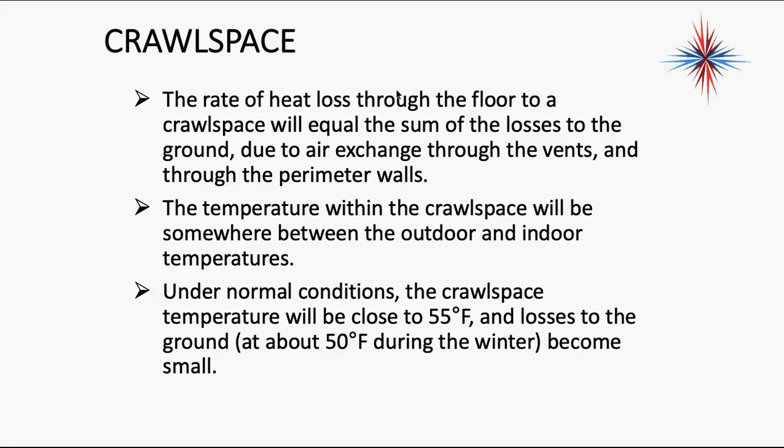The rate of heat loss through the floor to a crawl space will equal the sum of losses to the ground due to air exchange through the vents and through the perimeter walls. The temperature of the crawl space is somewhere between the outdoor and the indoor temperature. In other words, the crawl space won't be as cold as the outdoor environment, but it's going to be someplace between the indoor and the outdoor environments.